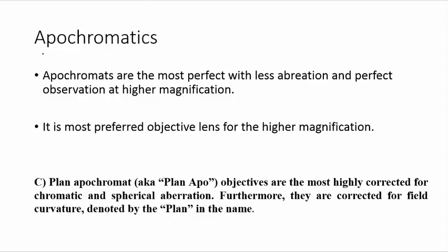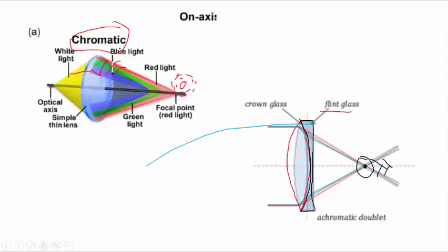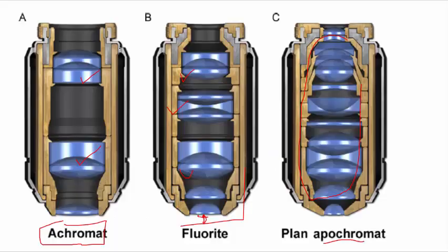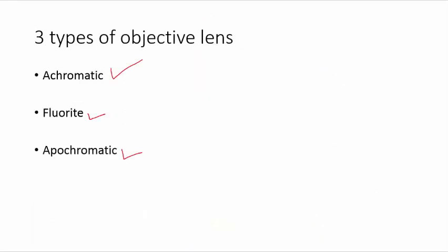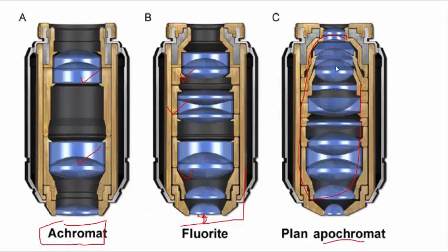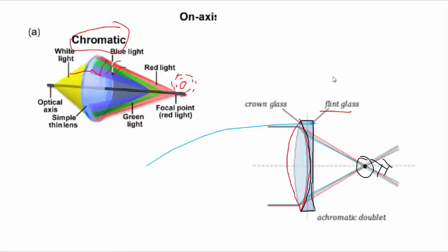The third and last type of objective lens structurally is the apochromat, which is considered the most perfect. It is considered perfect because it shows very little aberration at higher magnification. Inside the apochromat, there is the capability to eliminate both chromatic aberration and spherical aberration. Because of this, the apochromatic lens is considered very perfect. If you see the structure of the apochromatic lens, it is fitted with so many glass elements, which gives it the capacity to remove both spherical and chromatic aberration.